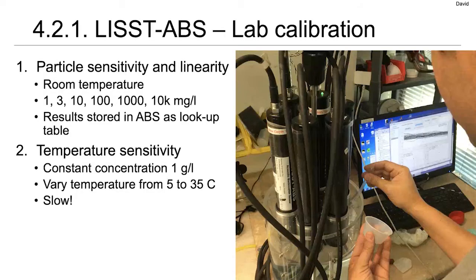Yeah, exactly. We go through a process. You can see we do 6 of these at a time. And it is rather labor intensive, actually. We found that this is a number that's manageable to do at one time. If you try to do more, then the mixing becomes more of a challenge. We basically do 2 major calibrations on these units. Number 1 is just measuring the sensitivity of the response versus concentration.